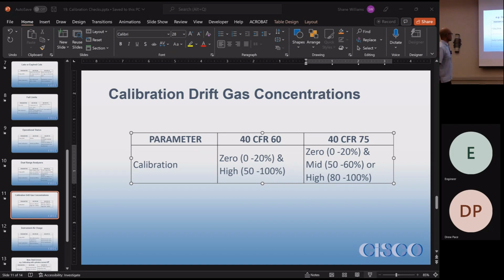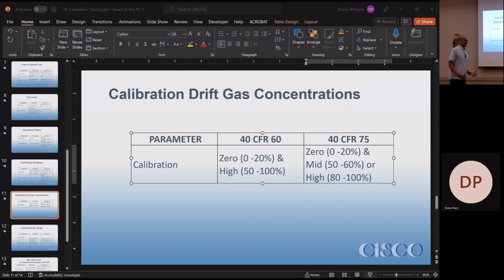Non-test errors, for example, calibrating with the cylinder turned off. This is the one that got scary for us. We talked to Kim Garnett at the EPA, and we had dealt with the Part 75 EPA many times. One of the questions we asked them was, hey, we ran a calibration, they didn't turn the cylinder on, or some other non-CEMS issue, and they told us it's a non-test, don't even report it. It shouldn't count against anything. And we felt pretty confident with that because that made sense.